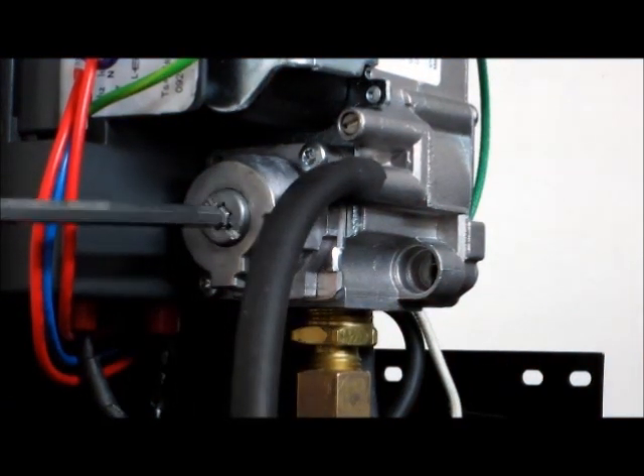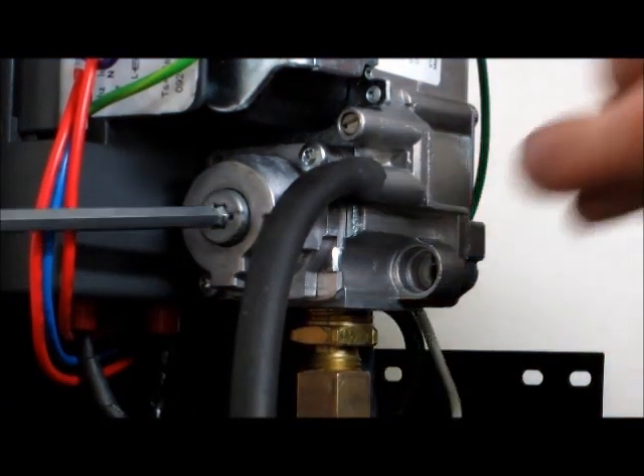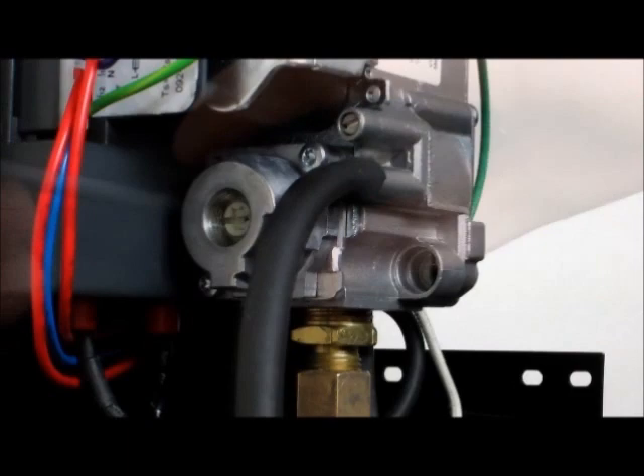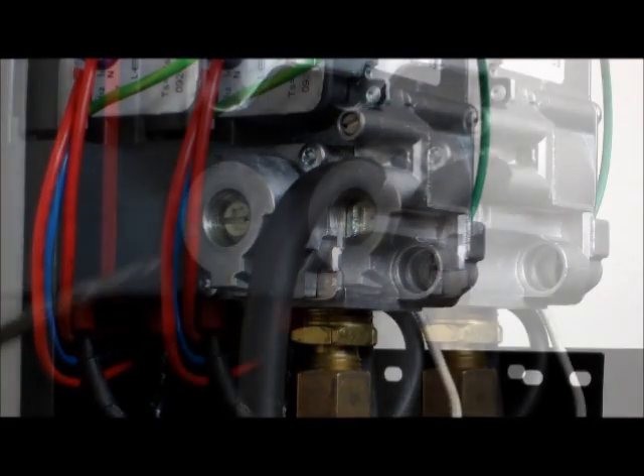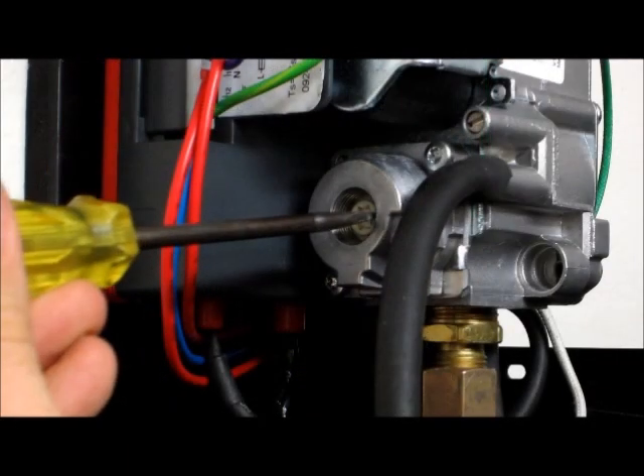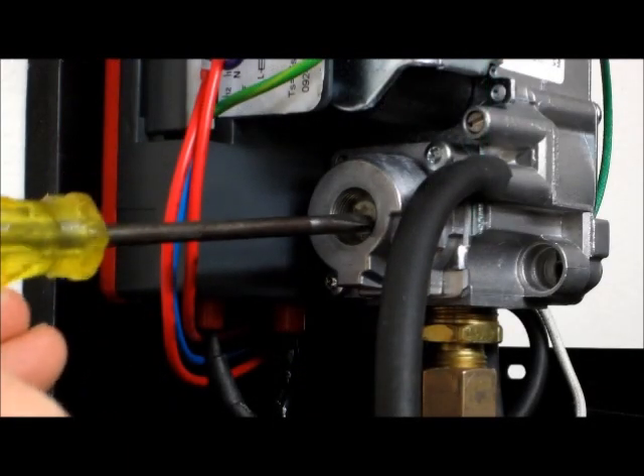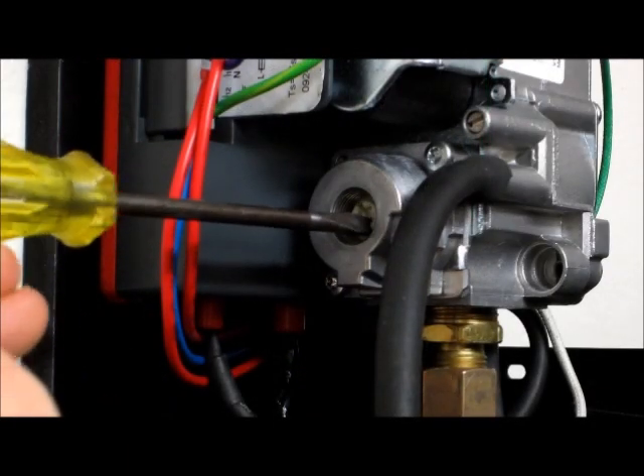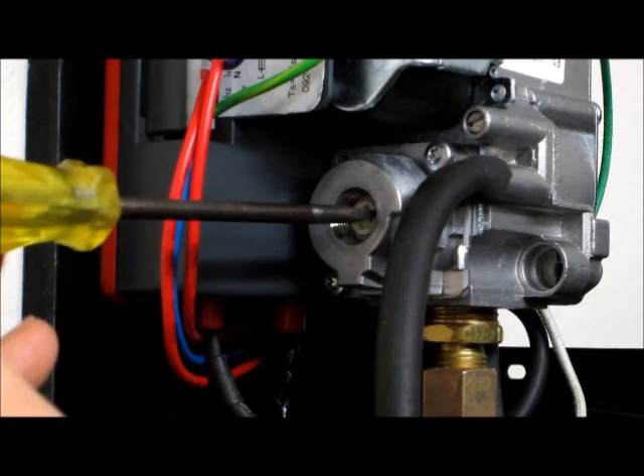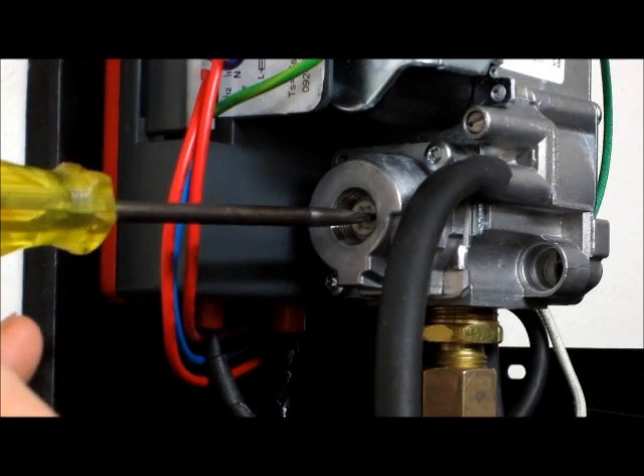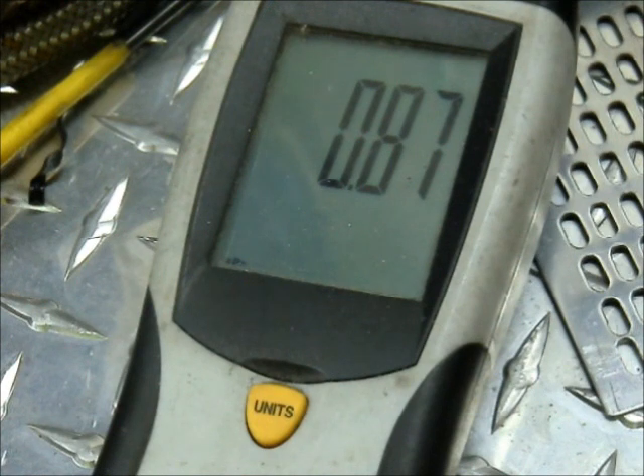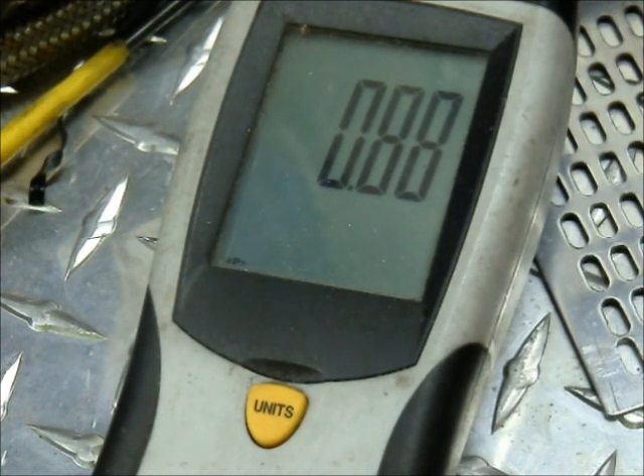Remove the regulator adjustment cover and start up the unit to allow the gas valve to open. Adjust the pressure by turning the regulator screw clockwise to increase pressure. The pressure must be set for appropriate gas type in accordance to your region specific pressure requirements as stated in the instruction manual provided with the heater.